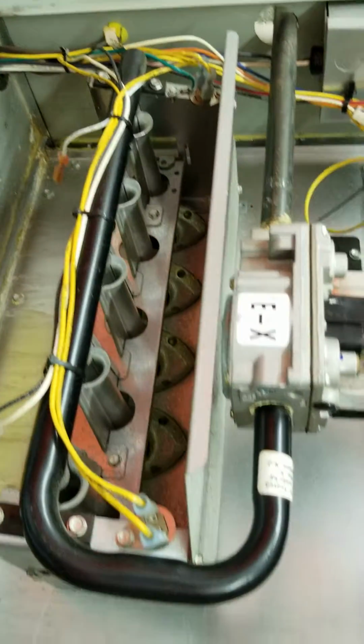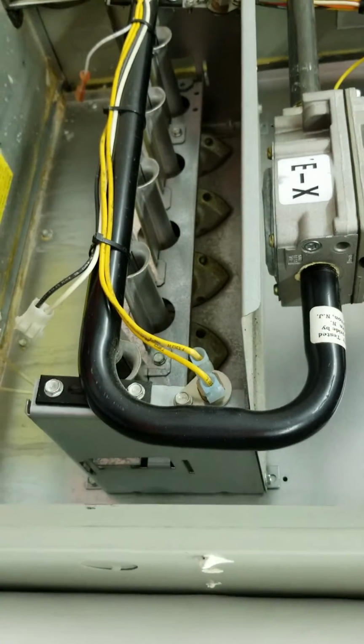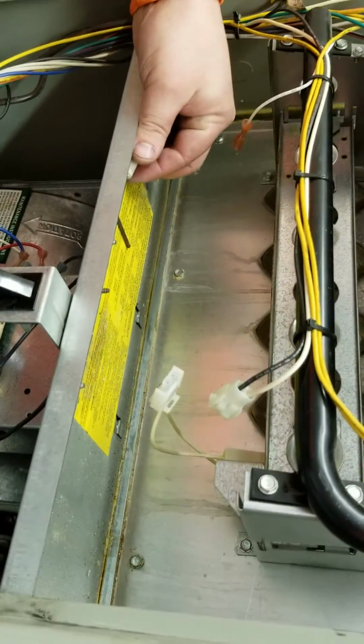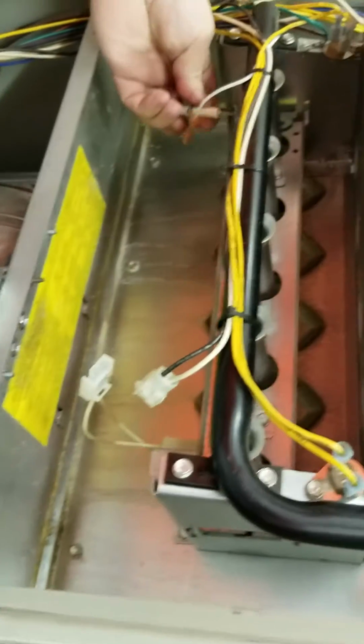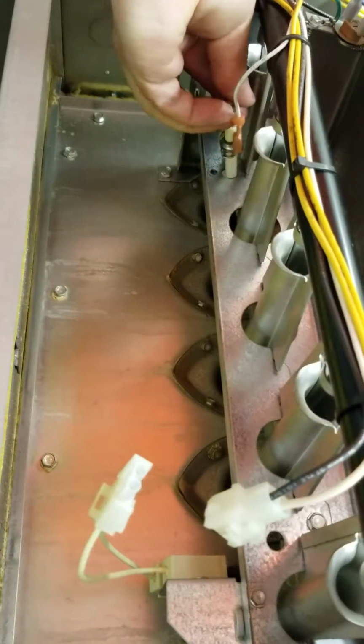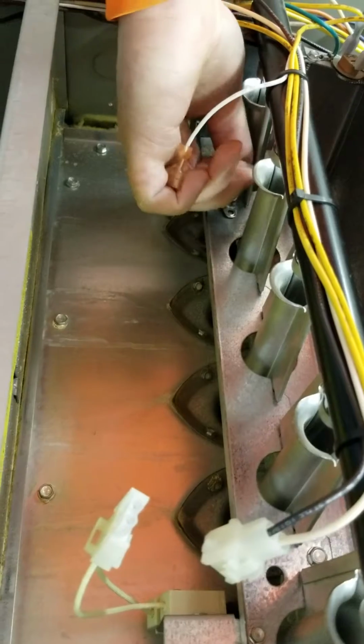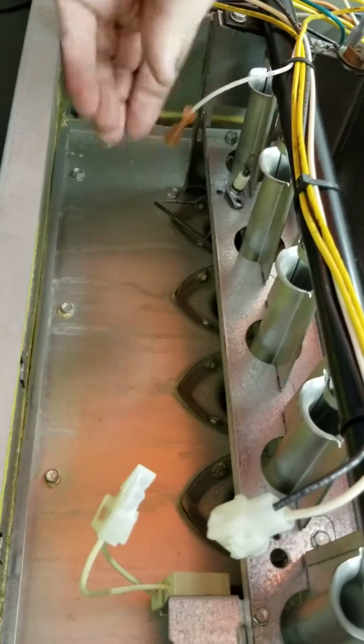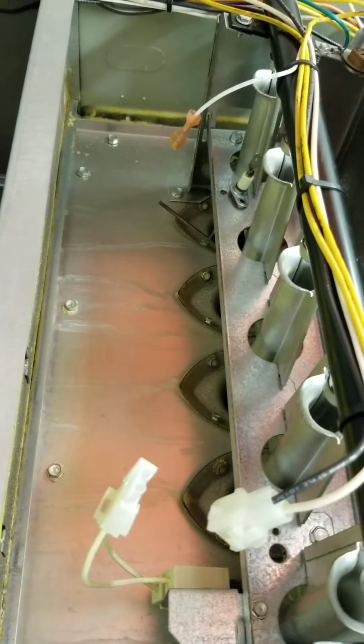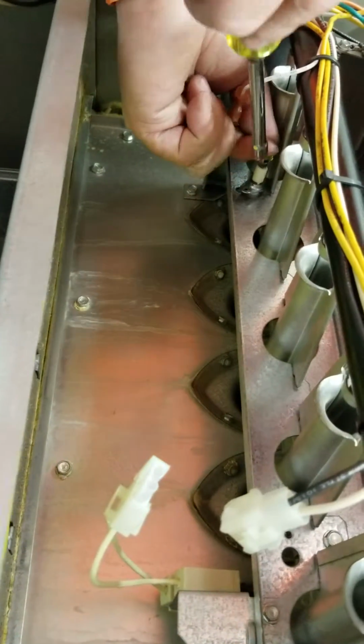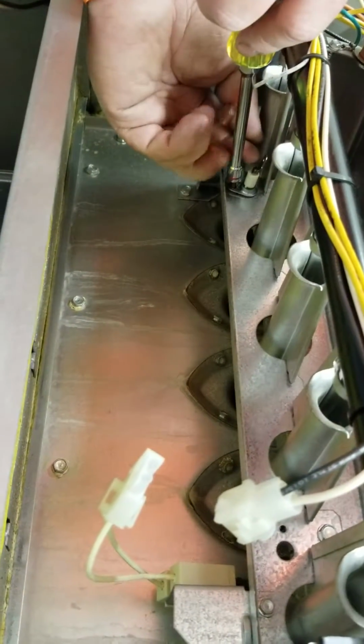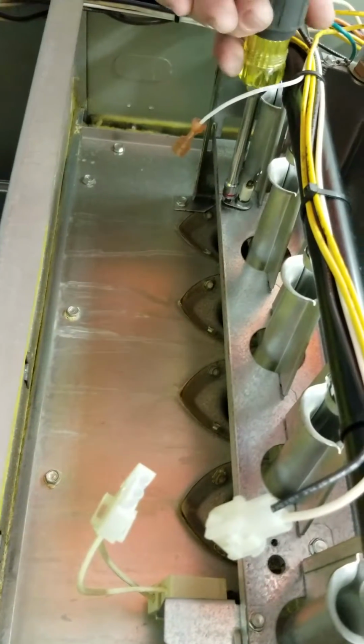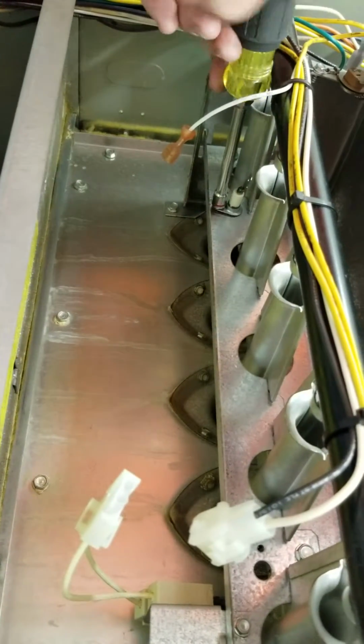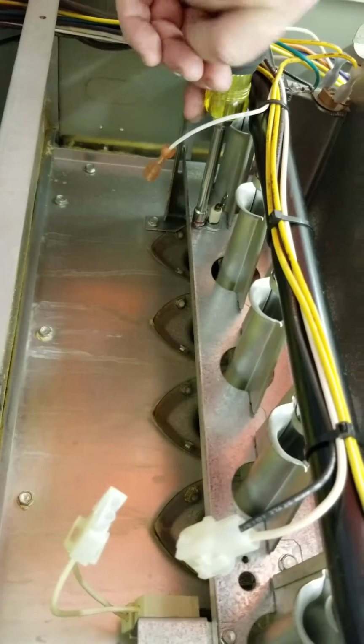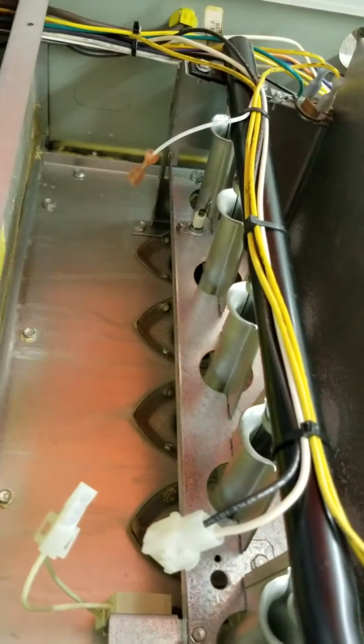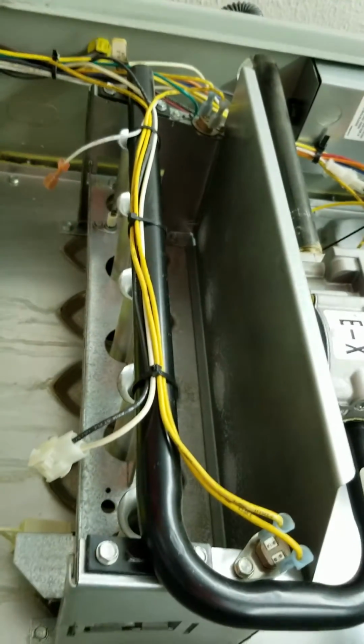There you go. Okay, go ahead and reinstall your sensor rod. Again, watching so that you make sure that the rod itself sits in front of the burner, the last burner, on the burner opposite from your hot surface igniter, because that's the safety feature. It has to prove flame all the way across in order for it to stay lit.